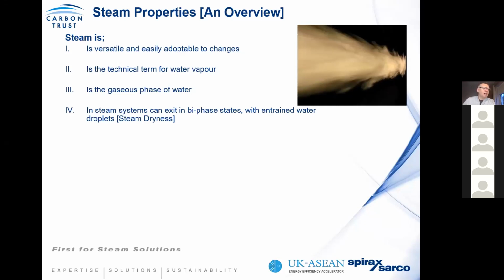What that means is that as steam starts condensing, it creates water. And even in a steam distribution system, you could have small droplets of water in the steam, and the volume of water is known as the steam dryness. So you're looking to get to unity or one, which is pure vapor. As you come back down towards fully condensing water, your dryness drops off, and effectively you want high quality dry steam.